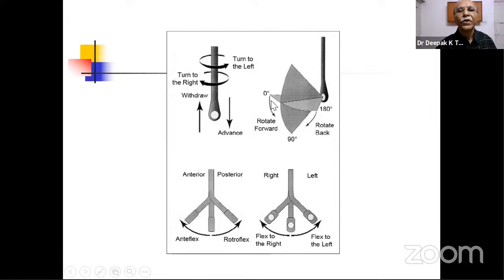And if you rotate the sector from 0 to 90 degrees, it is called rotating forward. And from 180 to 90, it will be called rotating backward, with the help of those two small buttons that I have shown you on the handle. Then this is the anteflexion and this is the retroflexion if it is flexed posteriorly, and this is flexing to the right and flexing to the left. So these are the four movements that you can perform. So the operator, while he's looking at the screen, should hold the handle with the left hand, and with the right hand, he is manipulating the probe. So there is a lot of hand-eye coordination that is necessary in order to obtain the image of your interest on the screen, and this needs practice.